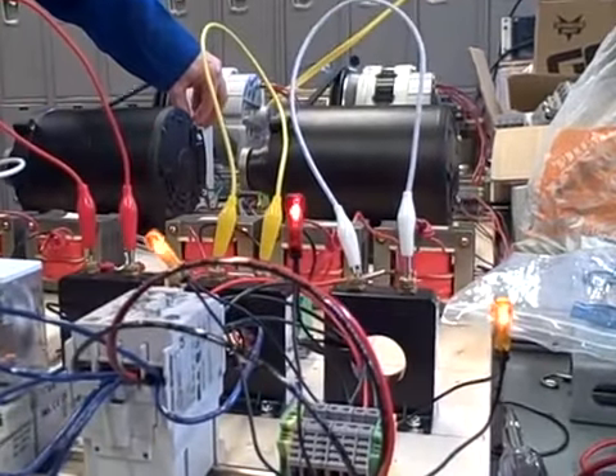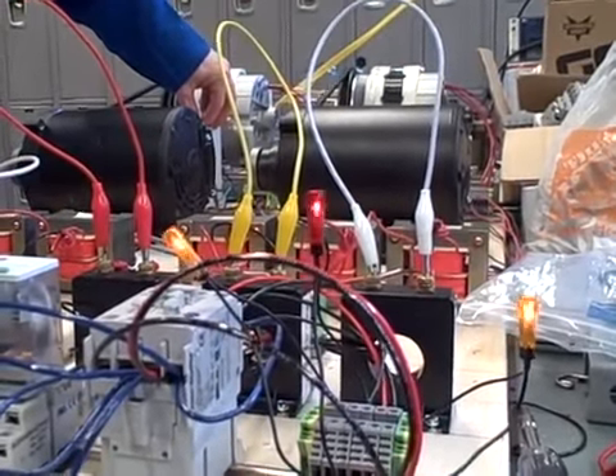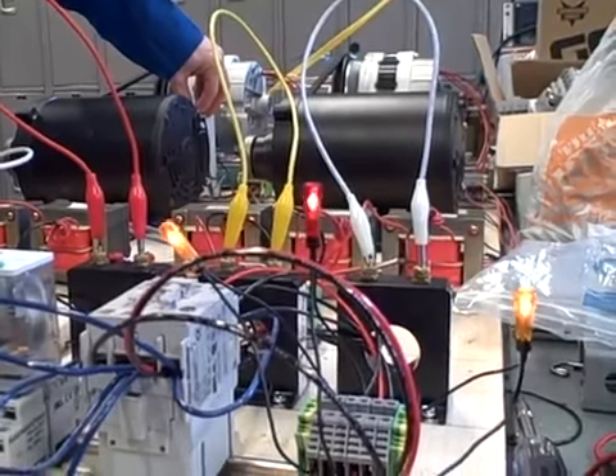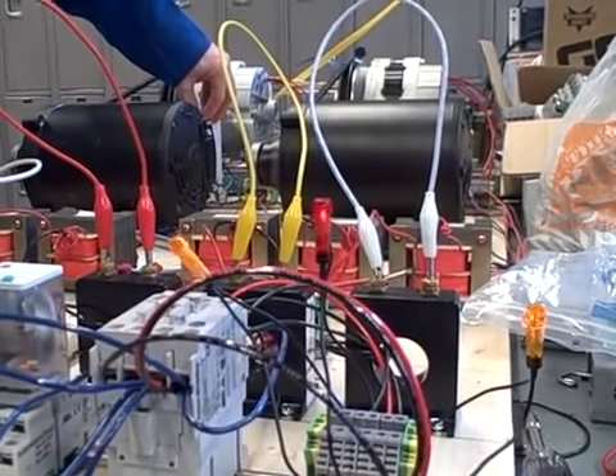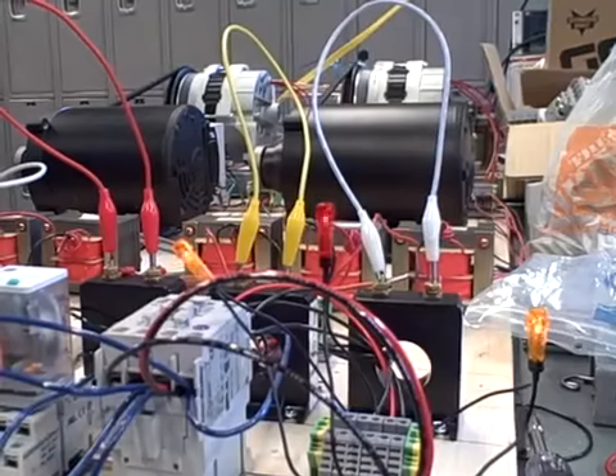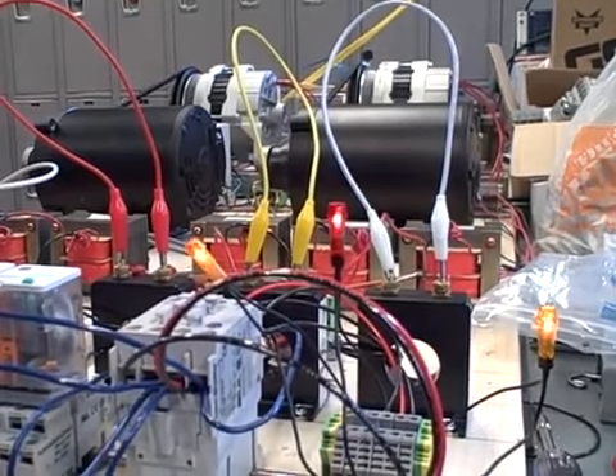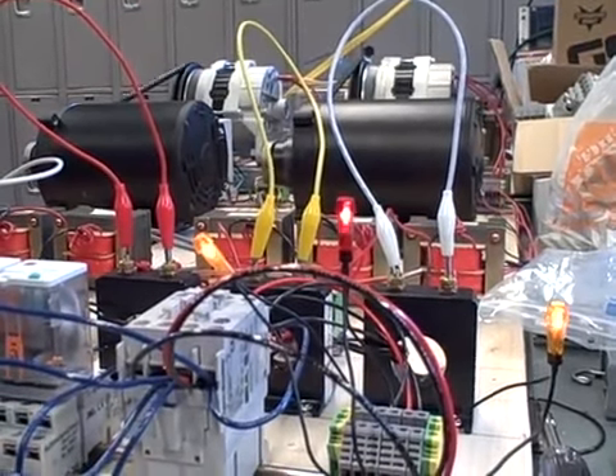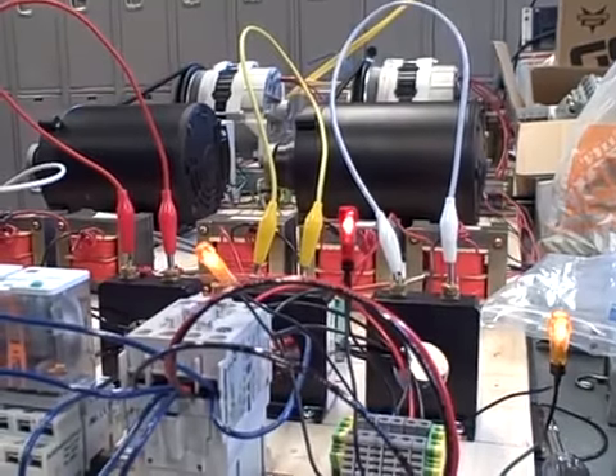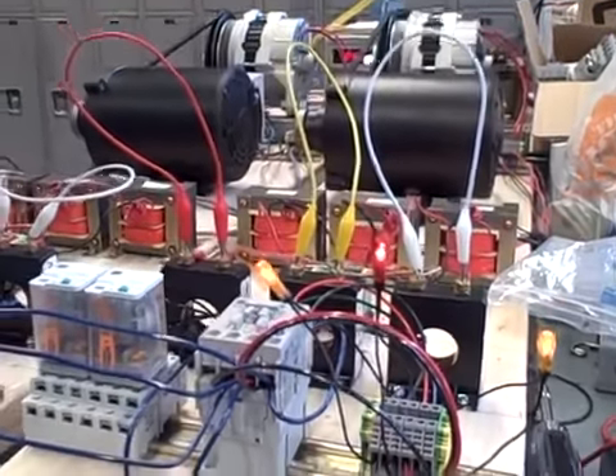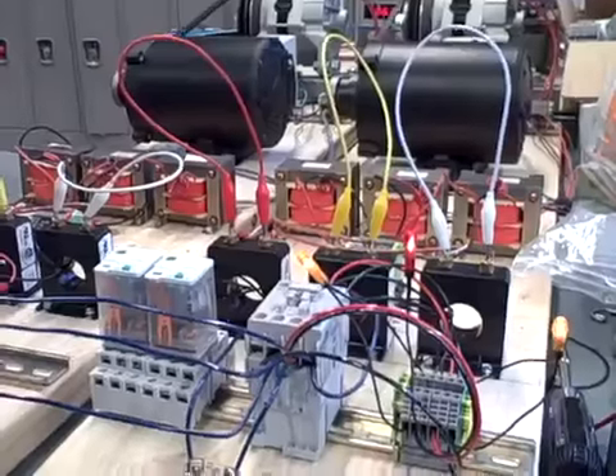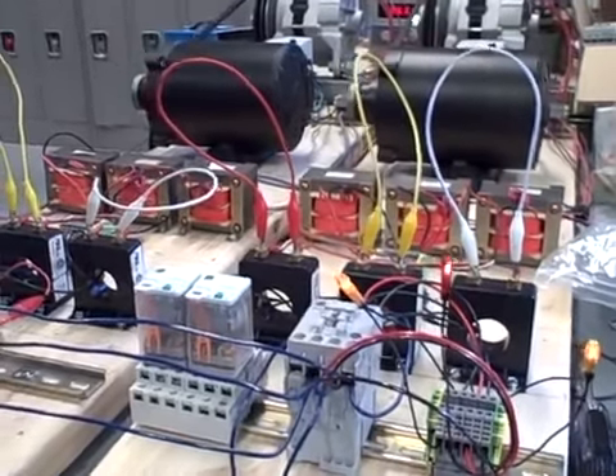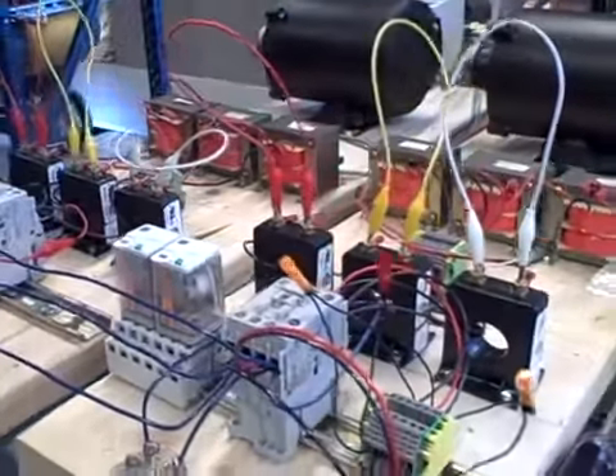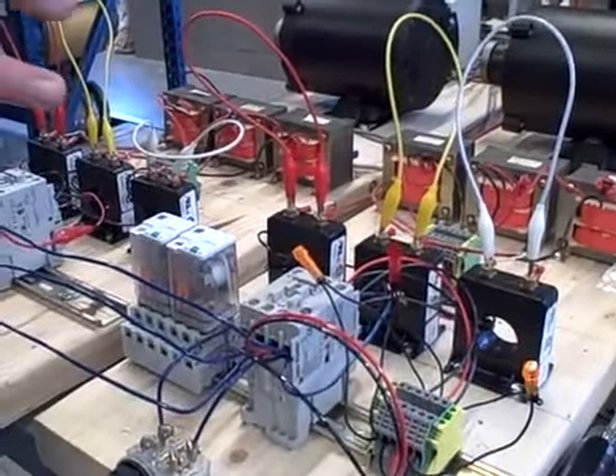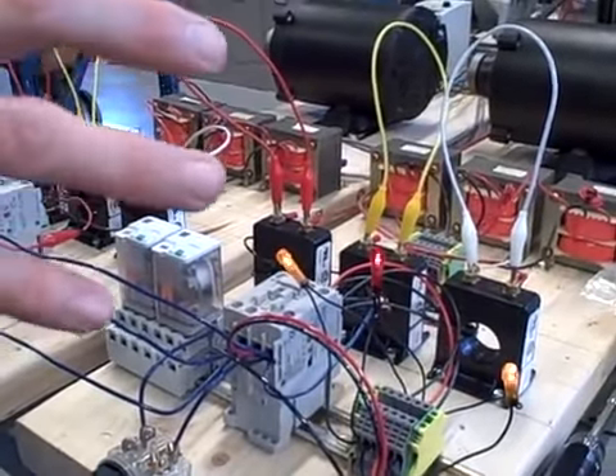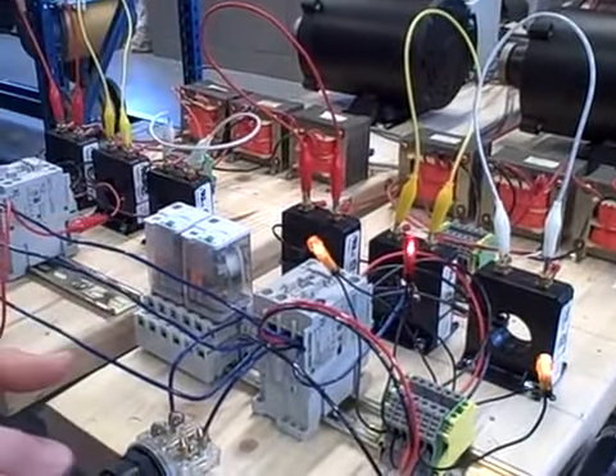I'll speed up the generator, it's blinking slower, speed up the generator, blinking slower. So what we see here is a case where the sine waves in these two generators are very nearly the same frequency, and they're rolling in and out of phase with each other a little more than once a second or so. So imagine 60 hertz versus 59 hertz. That's about what we're looking at here. I'm going to increase the speed just a little bit more on the slower generator until I get a slower blinking rate. Then I'm going to wait for the lights to go completely dark before I close my breaker.